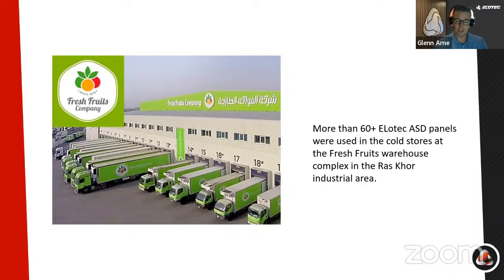You may wonder, where shall we place the aspiration detector then? You can easily place it inside the cold room. We recommend that because one of the main advantages is that you avoid temperature differences. Big temperature differences cause build-up humidity and condensation. The electronics and fire sensors inside the Elotec Aspect can manage temperatures down to minus 40 degrees, so remember that.